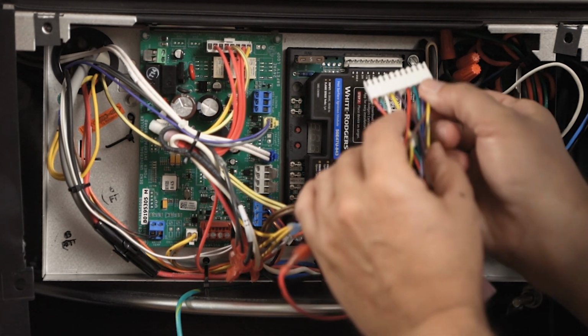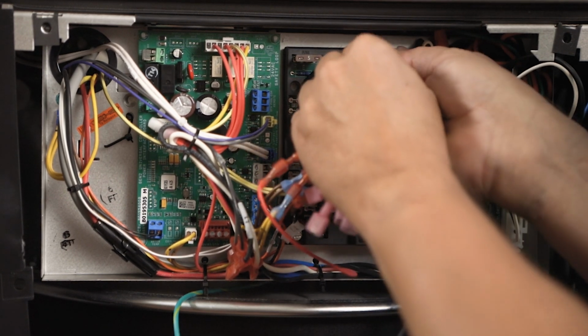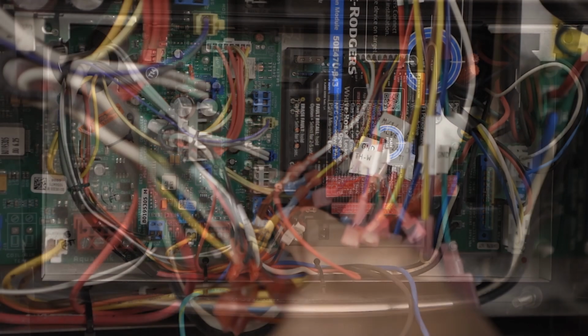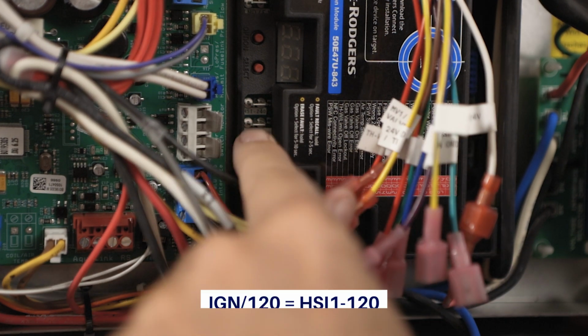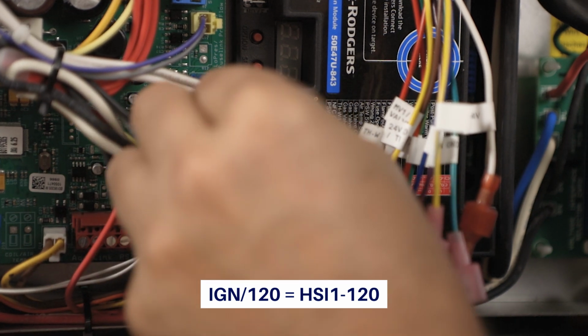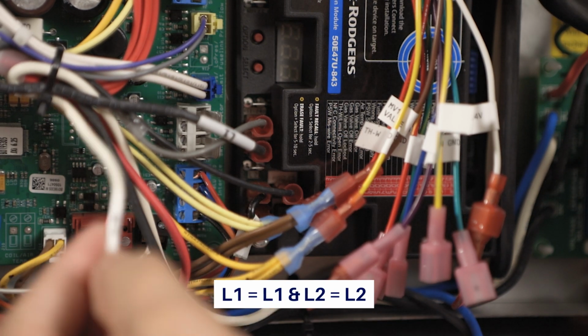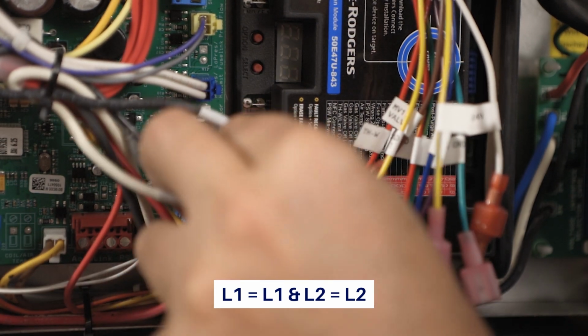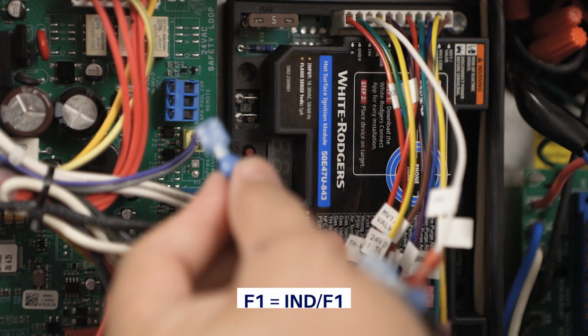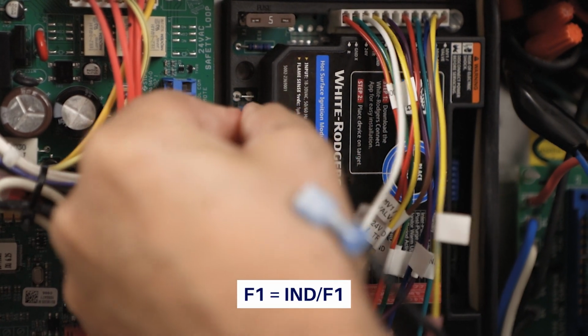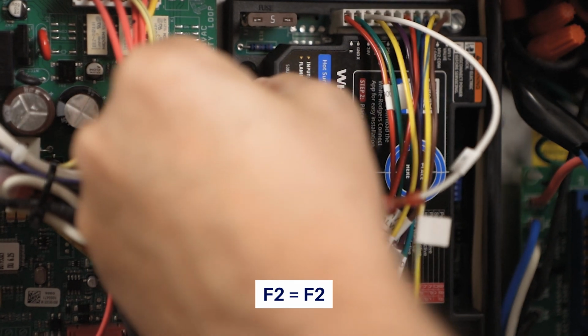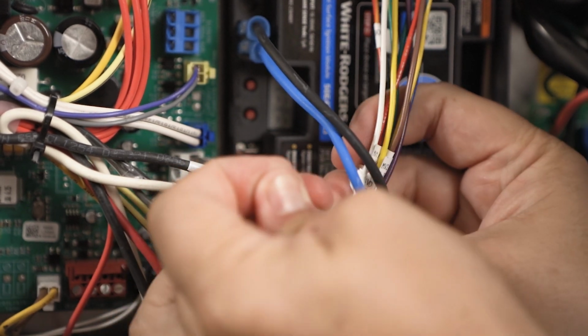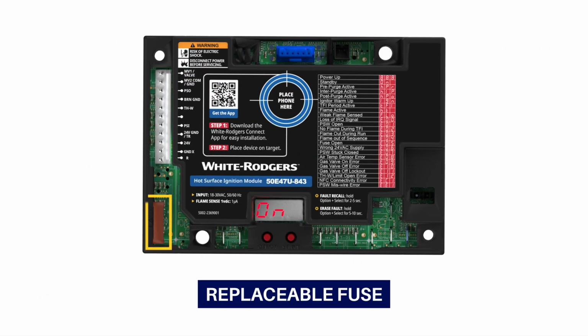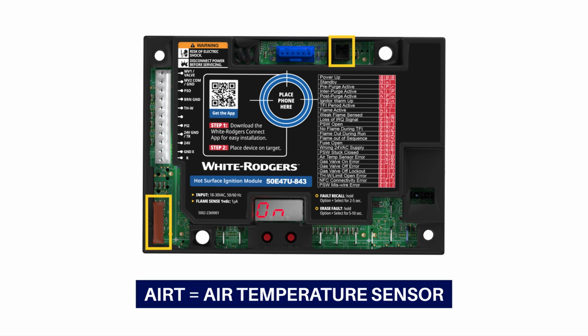Plug the 11-pin harness into the module. Install the remaining wires to the 50E47U-843 terminals. Connect ignition wires IGN/FS to HSI2-FS and IGN/120 to HSI1-120. 120-volt wires L1 to L1 and L2 to L2. And finally, inducer wires F1 to IND/F1 and F2 to F2. Check to make sure the wires are securely connected to the harness. Secure loose wires with the wire tie. This control also features a 5-amp replaceable fuse and an air temperature sensor connector.